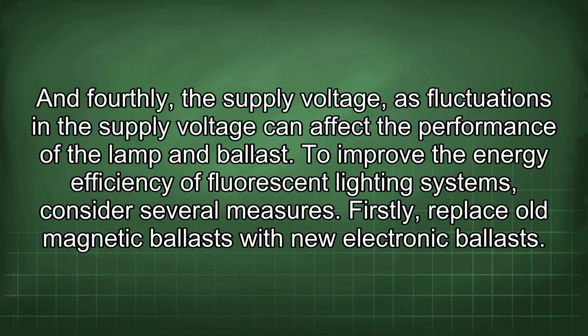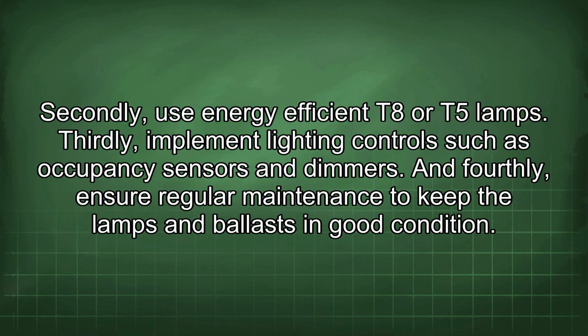To improve the energy efficiency of fluorescent lighting systems, consider several measures. Firstly, replace old magnetic ballasts with new electronic ballasts. Secondly, use energy-efficient T8 or T5 lamps. Thirdly, implement lighting controls such as occupancy sensors and dimmers. And fourthly, ensure regular maintenance to keep the lamps and ballast in good condition.